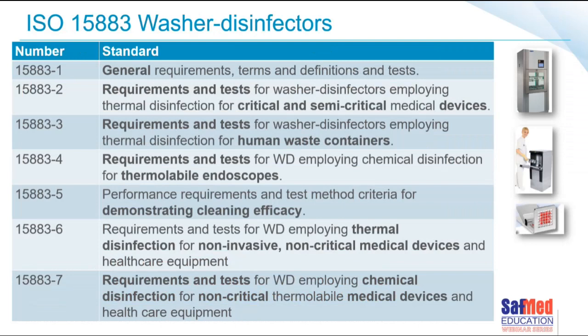When it comes to washer disinfectors, a washer disinfector used in the hospital setting must be bespoke — manufactured according to ISO standard ISO 15883. There are seven parts to the standard. Part one covers general requirements, terms, definitions and tests. Part two refers to the requirements and tests specifically for washer disinfectors with a thermal disinfection phase used for washing critical and semi-critical medical devices — the washers most of us have available in our CSSDs.